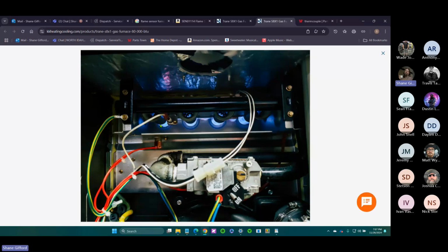But because this is in someone's house and not on a rooftop, you get a call. The first thing that's going to happen is your inducer motor is going to kick on, and it's going to pull a draft from the front of your burners through the heat exchanger, out the tailpipe, out the side of the unit. What that does is it basically proves that you do not have a cracked heat exchanger. If you have a cracked heat exchanger, you're not going to be able to pull the vacuum required by the unit via the pressure switch. And if you can't achieve that vacuum, then the system assumes there's something major league wrong. You probably got a cracked heat exchanger, so no way in hell do we want to fire off and dump a bunch of carbon monoxide on top of people's heads. So inducer goes, pressure switch makes.